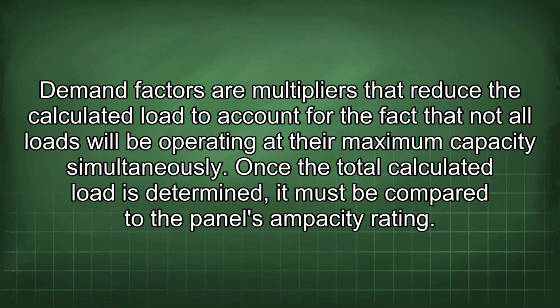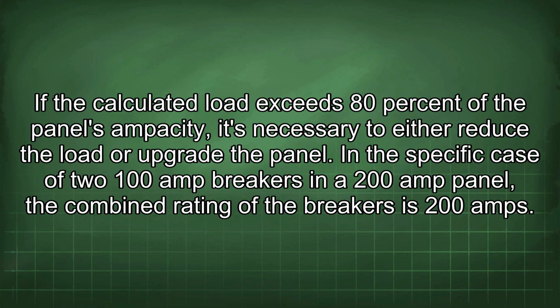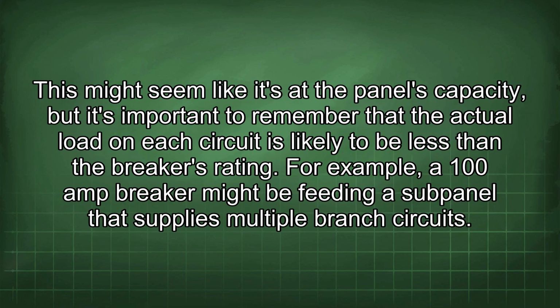Once the total calculated load is determined, it must be compared to the panel's ampacity rating. If the calculated load exceeds 80% of the panel's ampacity, it's necessary to either reduce the load or upgrade the panel. In the specific case of two 100-amp breakers in a 200-amp panel, the combined rating of the breakers is 200 amps. This might seem like it's at the panel's capacity, but it's important to remember that the actual load on each circuit is likely to be less than the breaker's rating.